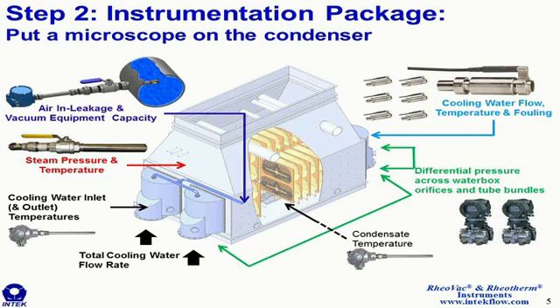So in addition to test grade steam pressure, cooling water inlet and outlet temperature measurements, cooling water flow is also needed. So a velocity traverse, dye dilution, and ultrasonic flows are recommended in the test codes. Differential pressure meters can also be used across differential producers to quantify flow rate after they have been calibrated. Air offtake monitors are used to measure air in leakage and vacuum equipment capacity. And finally, temperature and flow instruments are installed on the outlet tube sheets to monitor outlet tube temperature and flow rate. And with all this instrumentation in place, the 6 different components of excess back pressure that I showed you on the previous slide can be calculated.